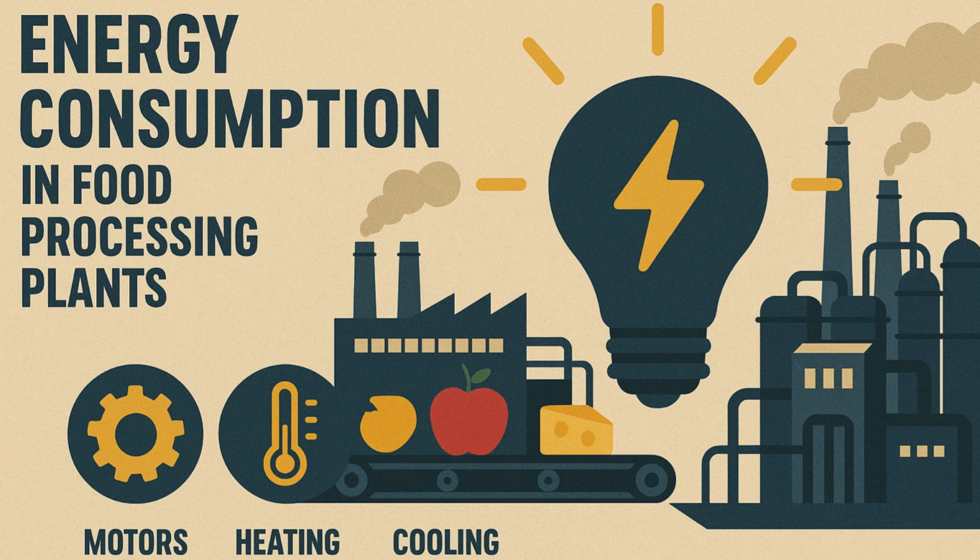Okay, so back to the example. Instead of the total energy to start a huge freezer over an hour, differentiation could tell you the rate of energy draw just in those first, say, 30 seconds, when the motor's really straining. Precisely. One source gave a great example. Analyzing the derivative, the rate of change of the energy curve during equipment startup, helped them spot problems. Like what? Well, if a motor's energy draw rate was suddenly much higher than normal right at the beginning, that could flag a potential mechanical issue, or maybe something needs calibrating. You catch it early, before it fails completely or just wastes a ton of energy over time. Exactly. It's about diagnosing efficiency problems as they happen, or even before they get bad.